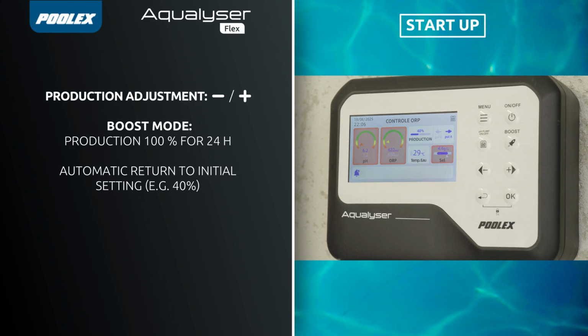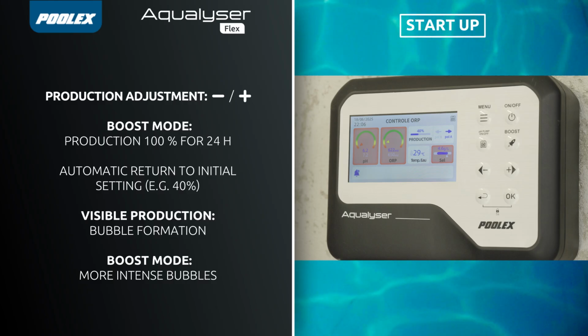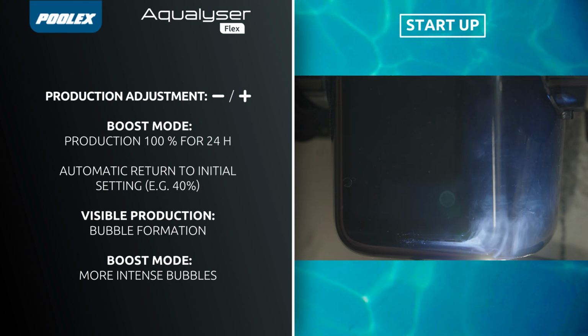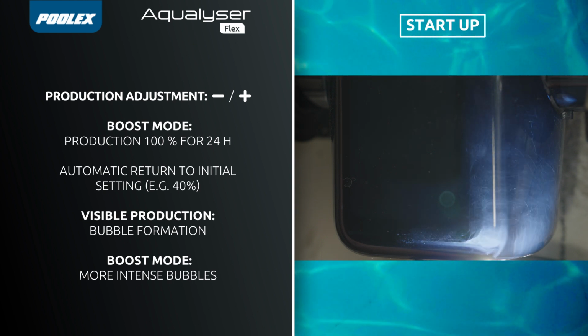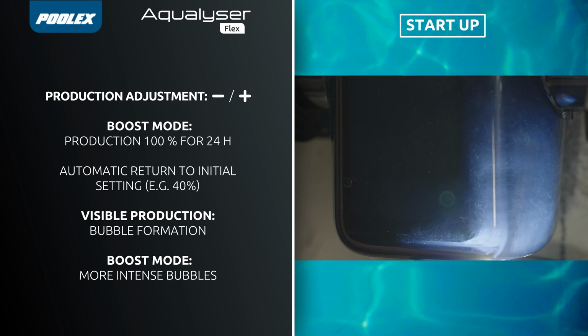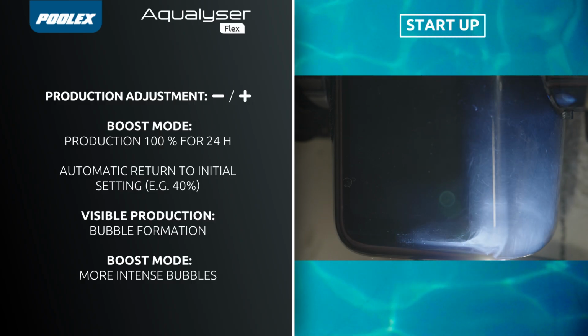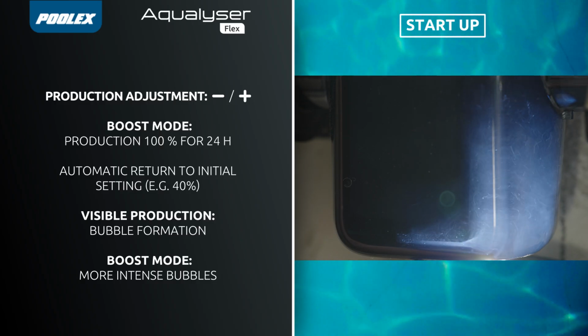The Aqualyser Flex then ensures automatic regulation of chlorine production according to the desired ORP set point. You can check that production is in progress by observing inside the cell. When the cell is active, you will see gas bubbles forming. In boost mode, this gas production is even more visible.